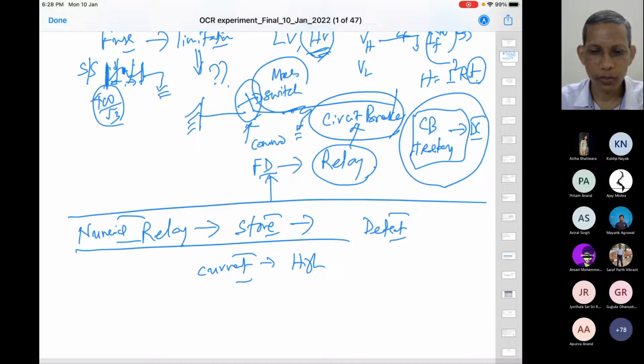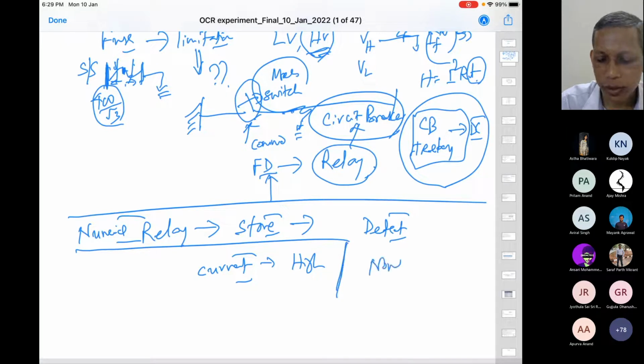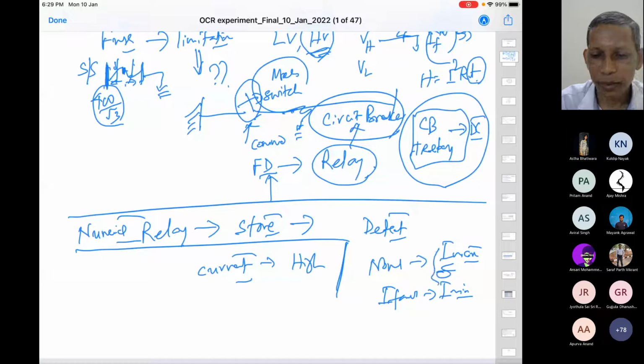So large current versus small current is a very good discriminator to be used in a numerical platform to discriminate fault situation and non-fault situation. For that, what to do? We have to find, in the normal situation, the maximum current expected, and during the fault, the minimum fault current expected. If there is a separation between these two, 5 amperes versus 10 amperes or 5 amperes versus 20 amperes, then you can make a judgment: if the current is larger than this, declare it a fault, and if it is smaller than this, keep silent. So this is a simple current-based logic you can put.